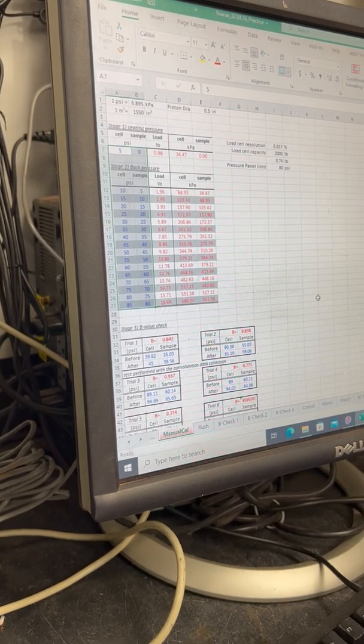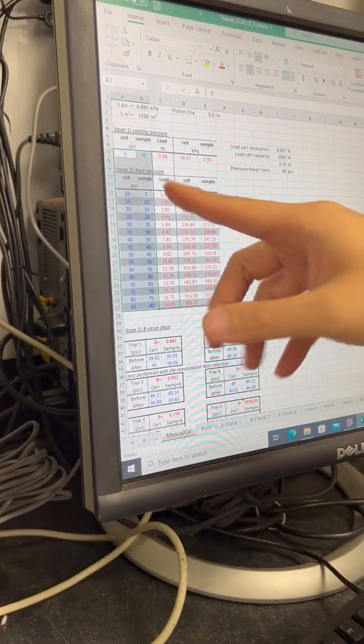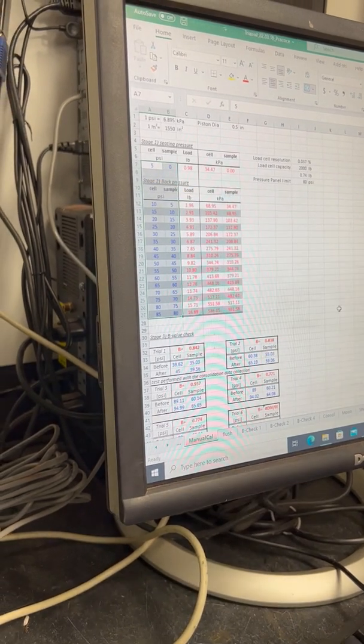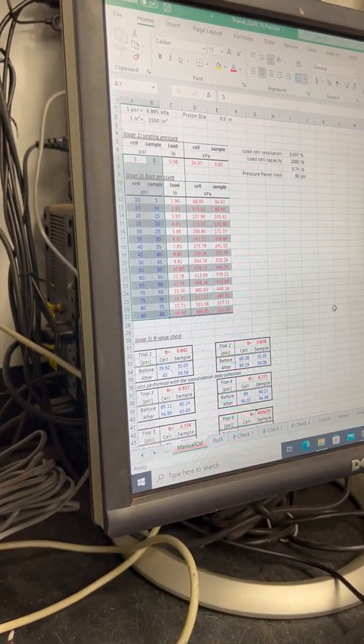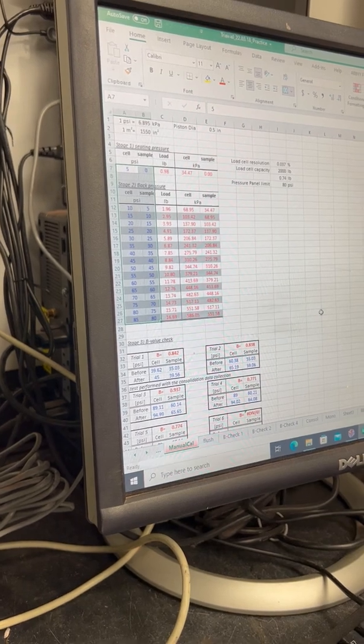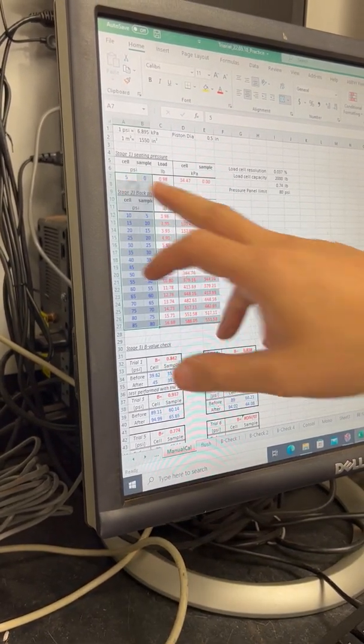You may want to change to even just one psi increments, especially at the seating pressure, because that gives you a very low stress level. For a practice test like this one, five psi is a good number to start with — it keeps things simple and makes your life a little easier.